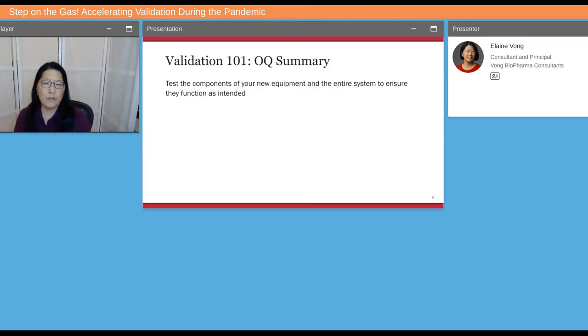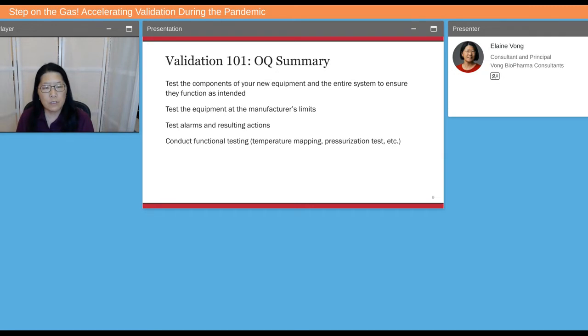For the OQ summary, we have testing the components of your new equipment and the entire system to ensure they function as intended. Testing the equipment at the manufacturer's limits. Again, as I pointed out, that's a soft requirement, but you might want to consider doing that to make sure the equipment operates as the manufacturer designed and that you catch it when you're installing it, not 5 years later when you all of a sudden want to qualify it at a wider range. Testing alarms and their resulting actions, and conducting any functional testing such as temperature mapping and pressurization.